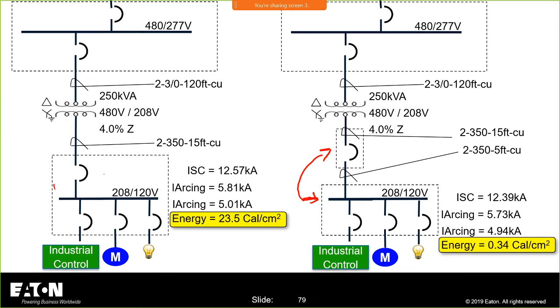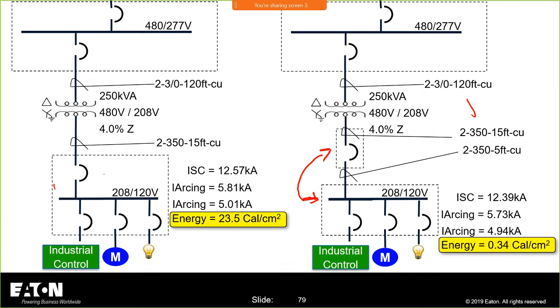Or if you were fortunate enough to plan it in place and buy a breaker integrated transformer, I'm just going to throw these three letters out there, BIT. If you're a bit head, I've been called a bit head before, you'll love that. My digital world. So that is a world of difference. And if you throw a fuse in there instead of just a fusible disconnect switch, you take that point to less than a calorie. You're wearing gloves. You're wearing the minimum PPE.